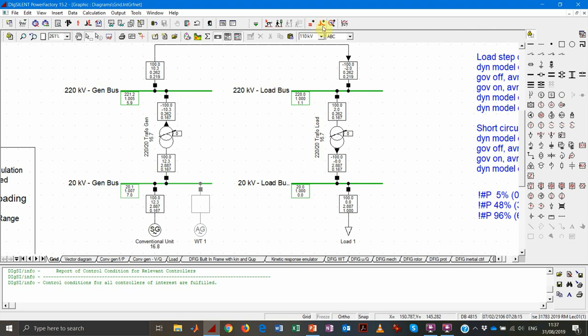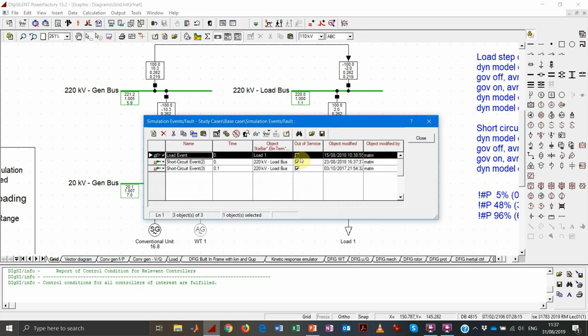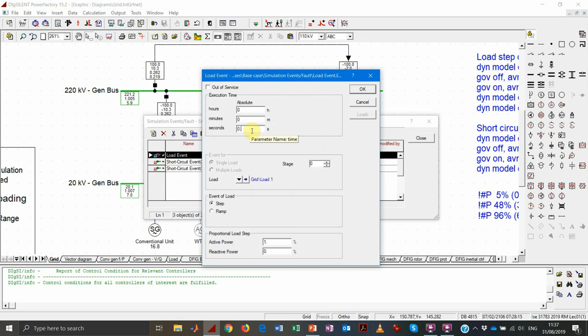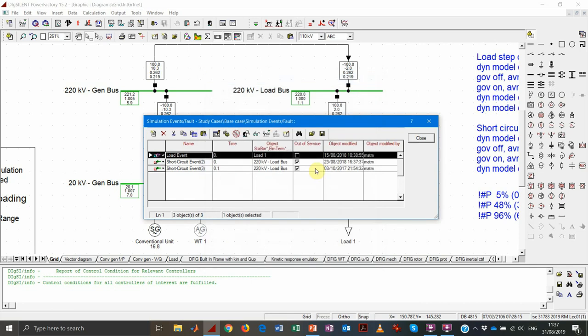We have a feasible load flow solution. Now let's look at the dynamic analysis. Under the events, we can set a load event — or later, short circuit events or generator events. The load event already preset will apply a step with an amplitude of 1% at t equal to 0. First, however, we should perform a dynamic simulation without any event, to confirm that nothing happens in the system if we don't perturb it.